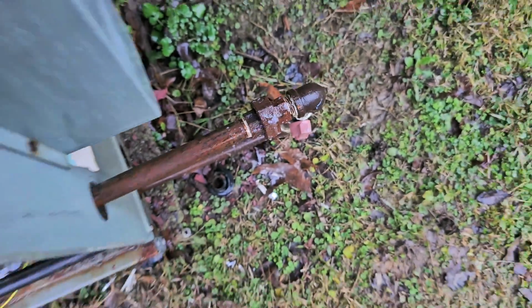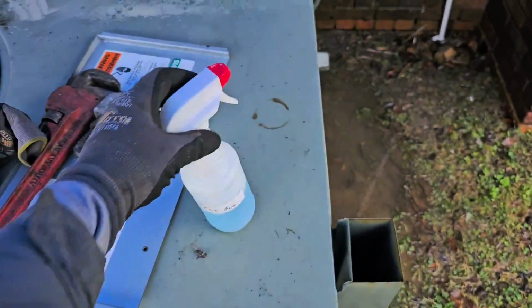All right, so no gas leaks. Good. A couple things I like to do before I start up a packaged gas unit after I've replaced the heat exchanger. One is make the customer aware that whenever you install a new heat exchanger, it's got some oil on it. That oil is going to burn off and it's going to produce some smoke. So we want to make them aware, especially if we're working in a commercial building where they've got a fire alarm system. You want to make them aware because the fire alarm may go off.